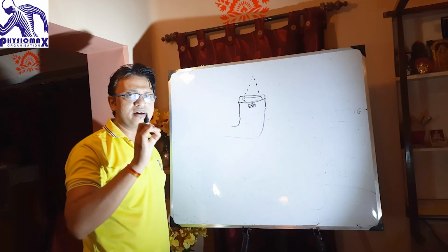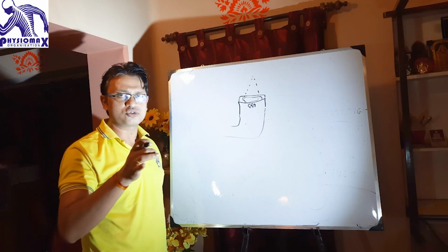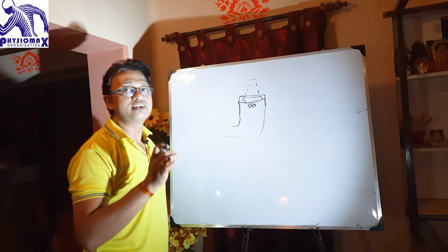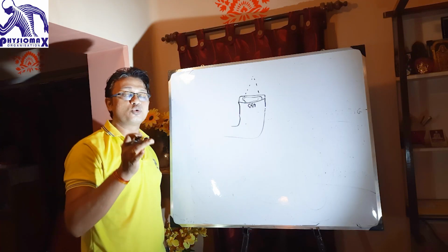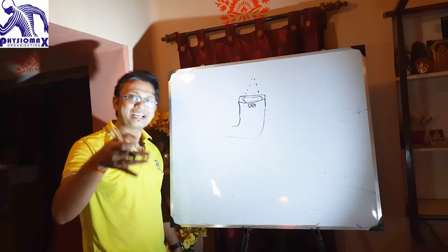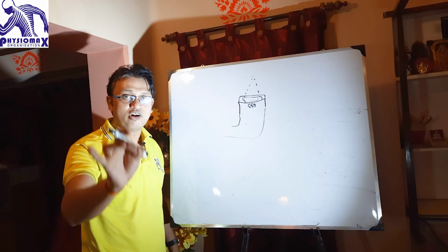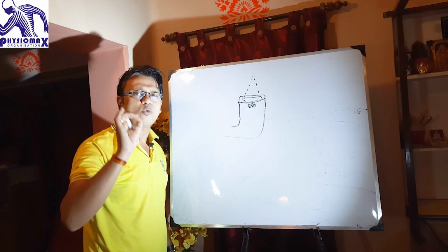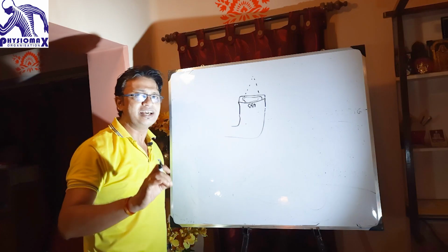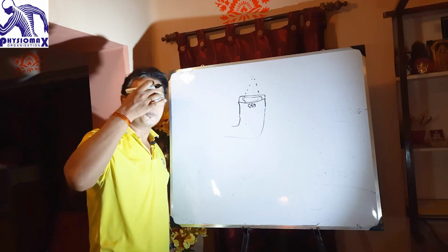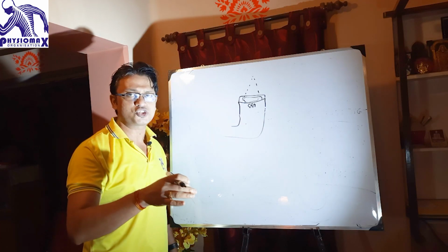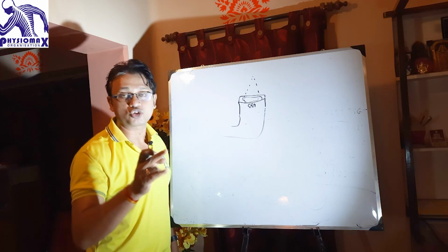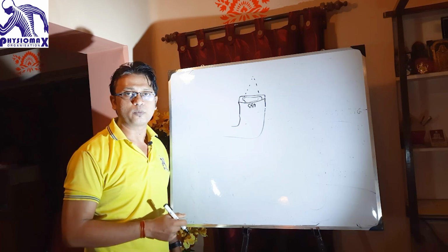Does the water which is poured above the transducer need to be vaporized, or does it need to make a fountain? So to understand the fountain test, just pouring the water above the transducer does not mean the ultrasound is proper, and if it is vaporized it does not mean the ultrasound is working in a proper way.